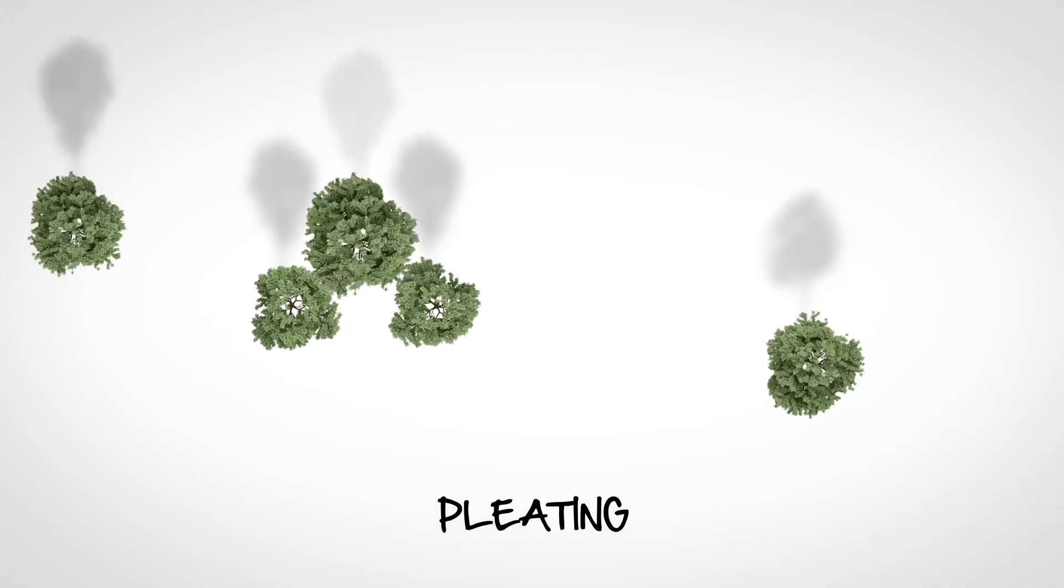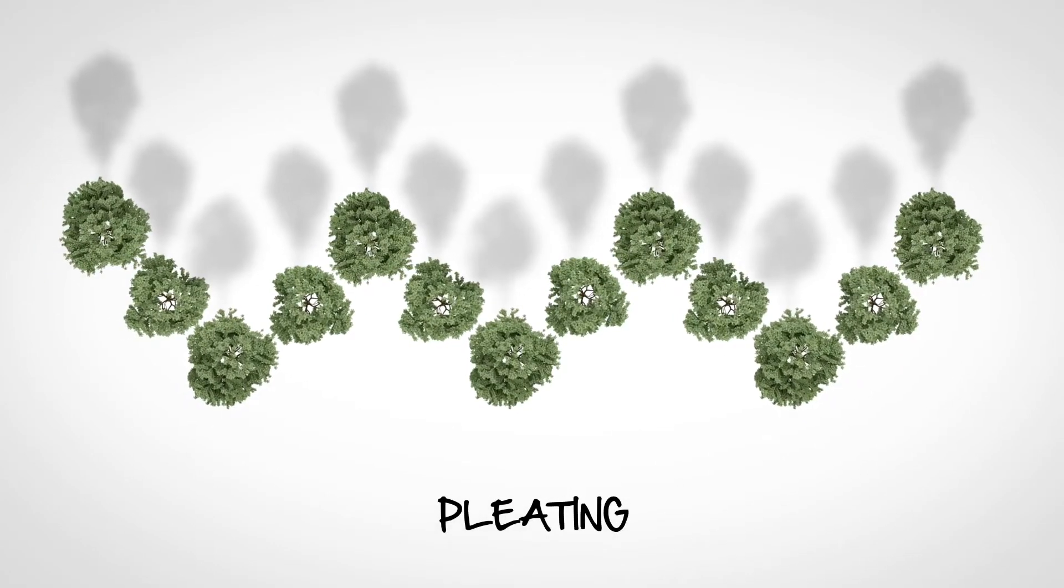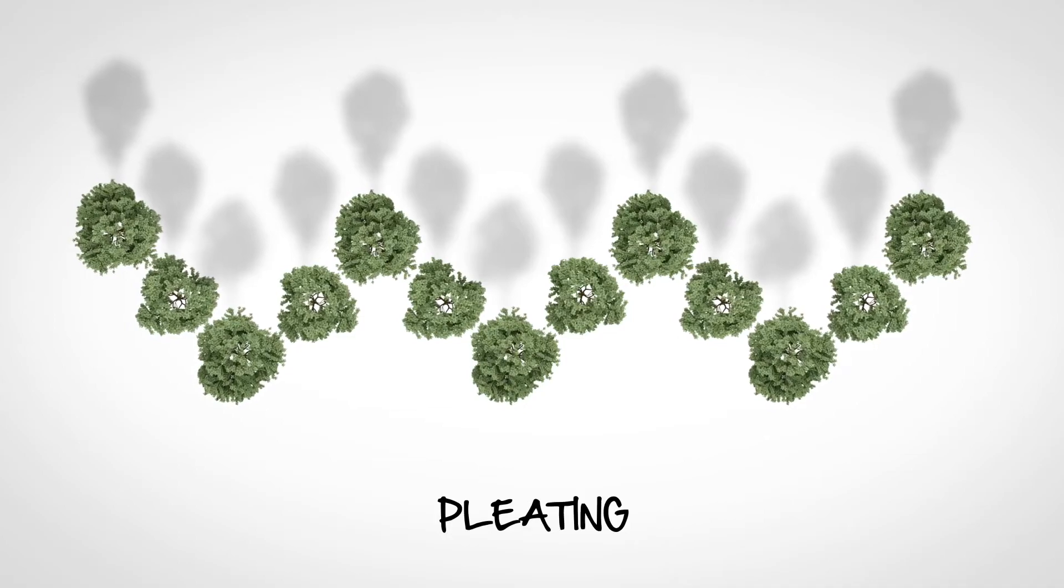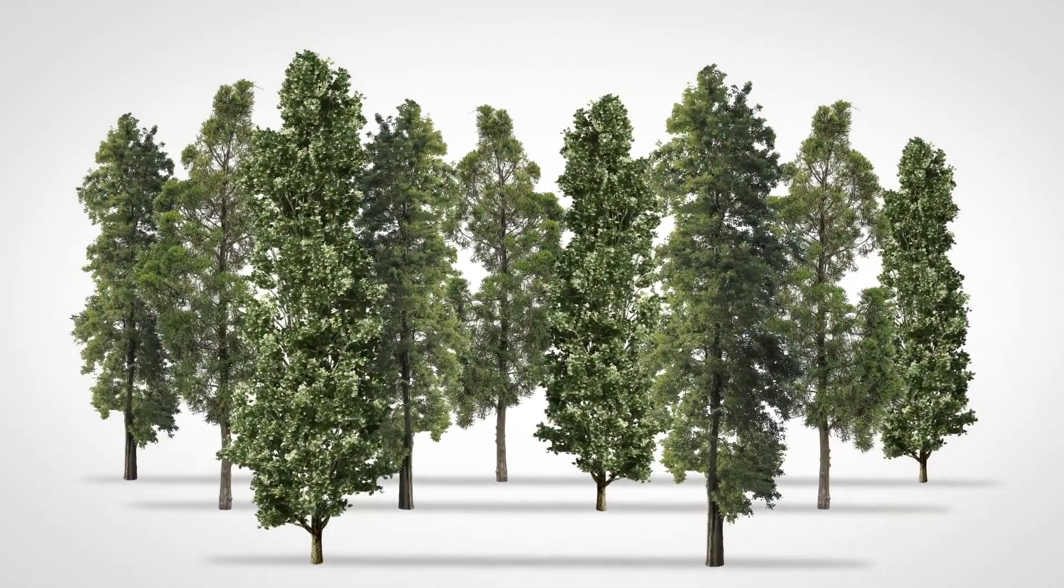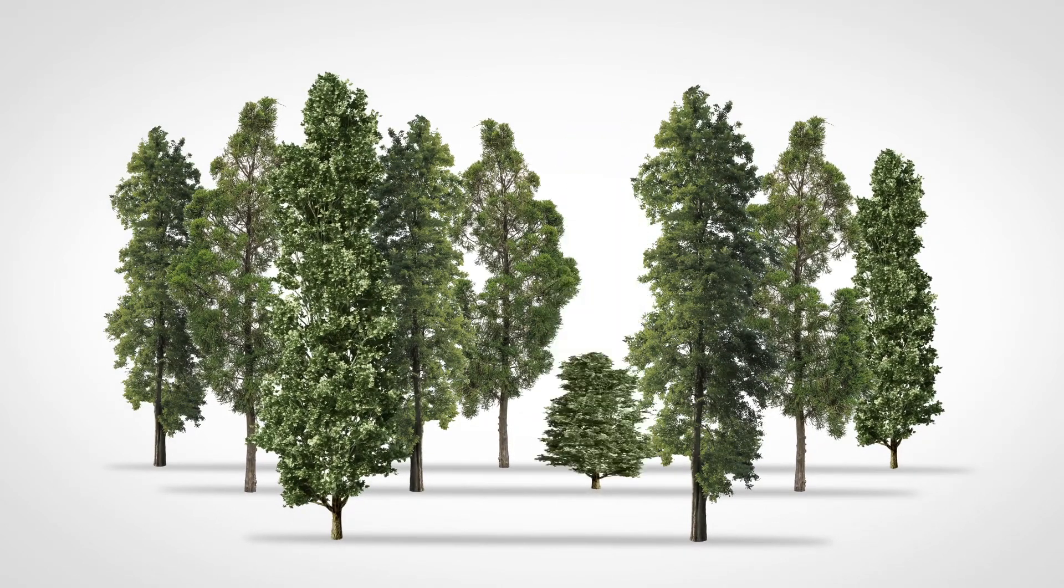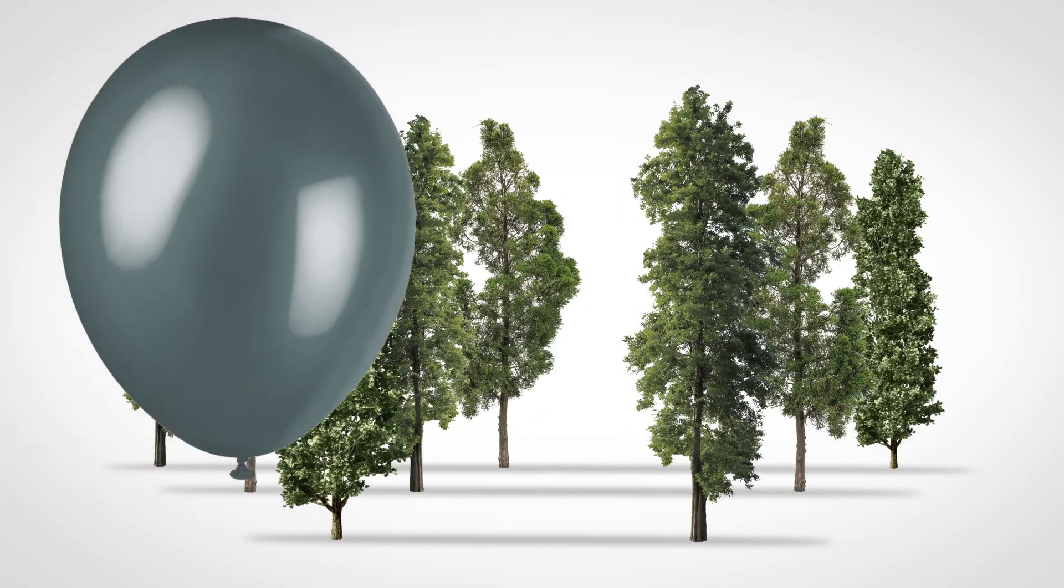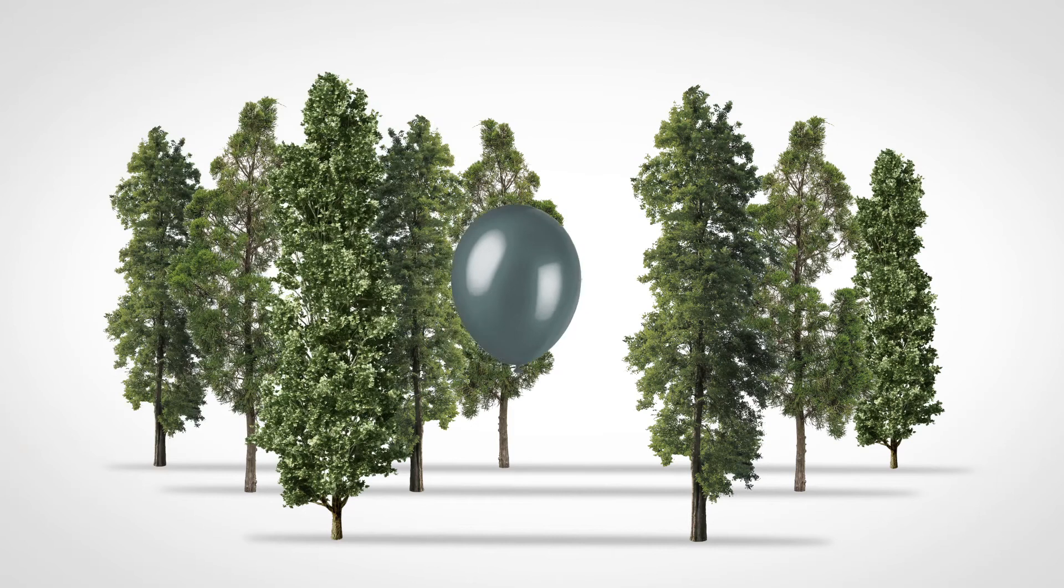There is another technology called Pleating. Pleating increases the filtration surface, or in our metaphor, the number of trees in the forest. But it also increases the risk of cracks, and therefore the risk of oil carryover, and thus, poor air quality.